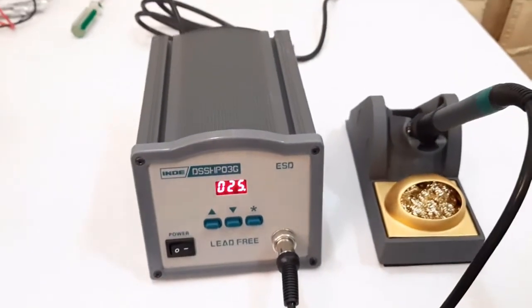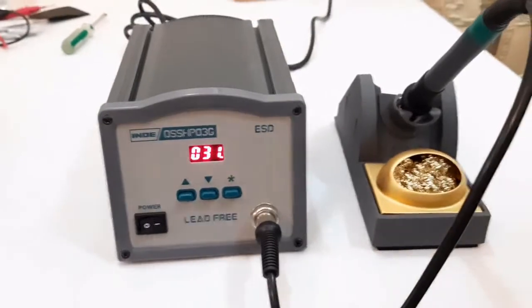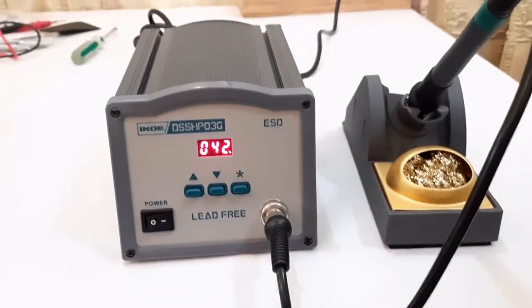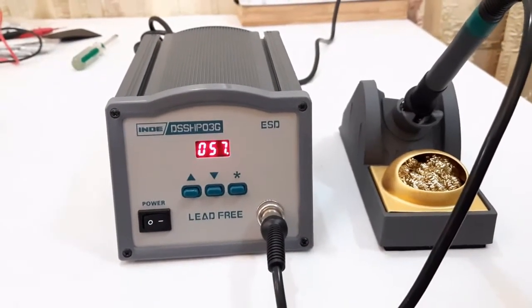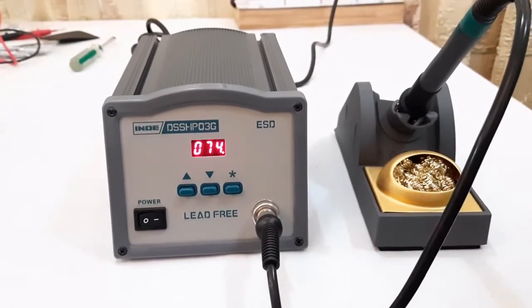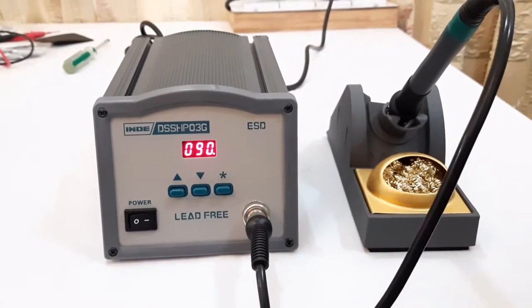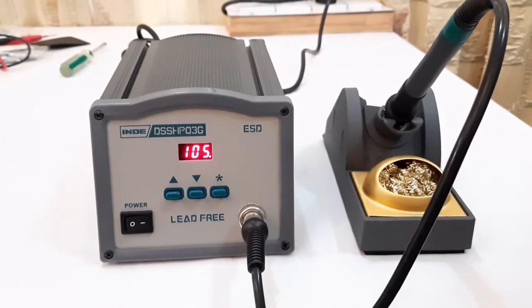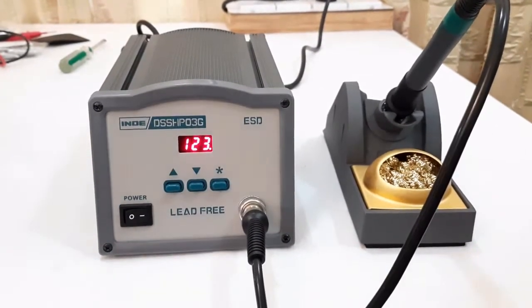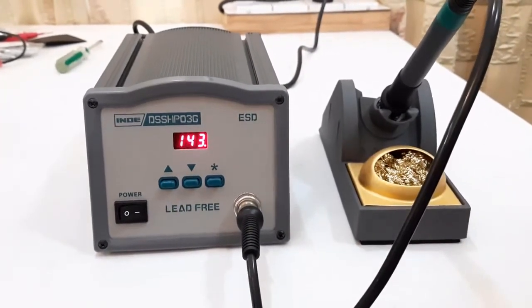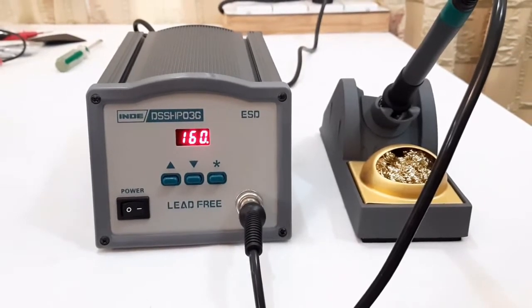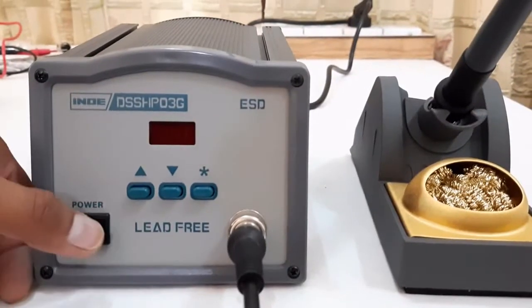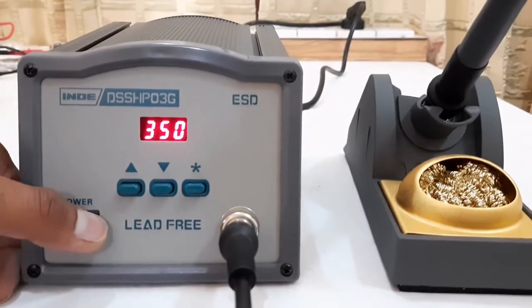Now we can see the temperature is rising. Earlier we were facing HE error, but now that error has gone, and now the temperature is rising gradually, and it will achieve the set temperature soon. So in this way this heating element error can be resolved. Another problem we can encounter is the SE flashing on the display.